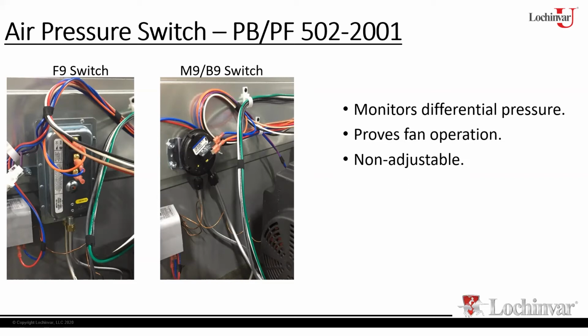Now, one thing that you'll notice about both of these switches, for the F9 as well as for the M9, for the 502 through 2001, is that they're differential switches. So basically, I'm looking at the discharge of the blower versus the pressure inside the combustion chamber, right? Because they're differential, it serves not only the low air function, but also serves as a block flue function. Right? So that means if something happens and the vent gets plugged up basically completely, and the pressure increases inside the combustion chamber, then that causes the differential between it and the outlet of the blower to drop.